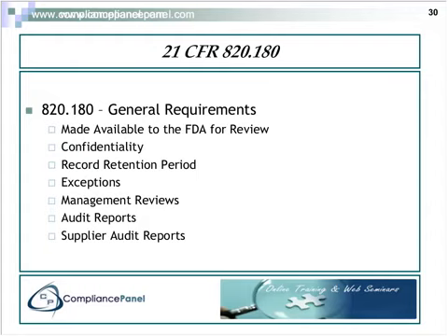confidential, because any and all information gathered by the FDA becomes part of public record under the Freedom of Information Act. So under the Freedom of Information Act, if you have a supplier, for instance, that's supplying you with a finished device that's an accessory to your device, you can apply to the FDA to say, I would like a copy of their last establishment facility audit, and you can obtain that. So anything that you feel is confidential must be marked that way, or it can become part of public record.